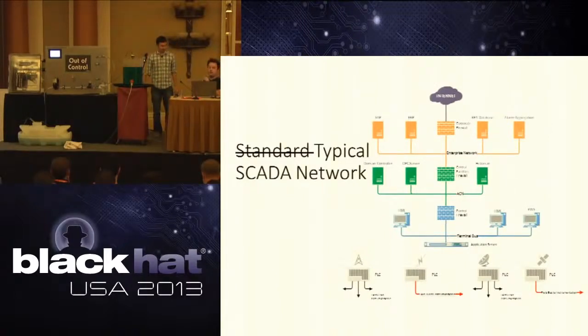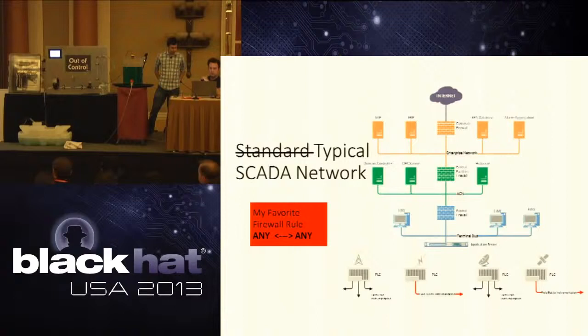Yeah, and this is a typical SCADA network. This is the recommended network architecture where we have multiple firewalls in place to segregate the traffic types. However, a lot of the firewalls that are implemented are really just put in place because somebody needs to comply to a standard, and they end up leaving their firewall just allowing all traffic to pass, which isn't really a firewall at all.